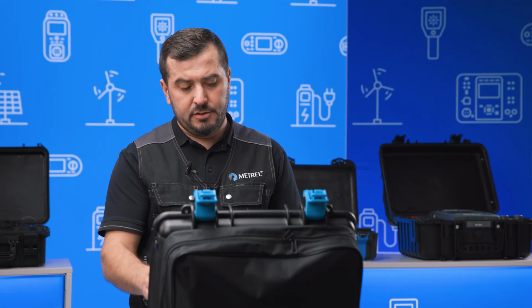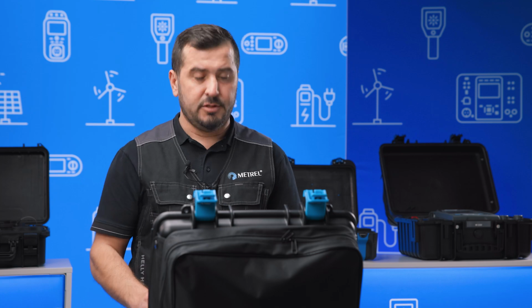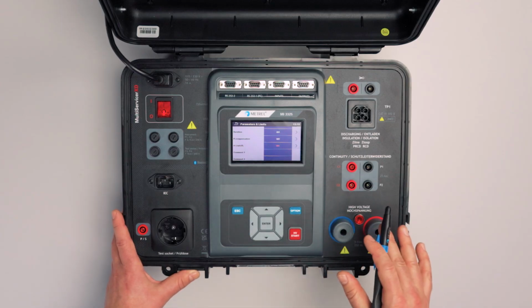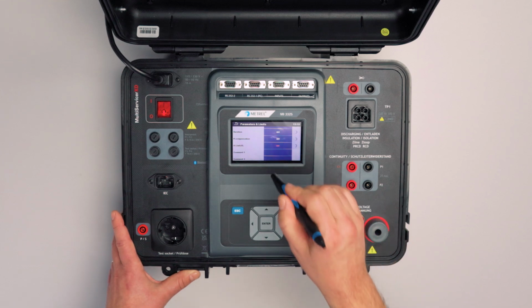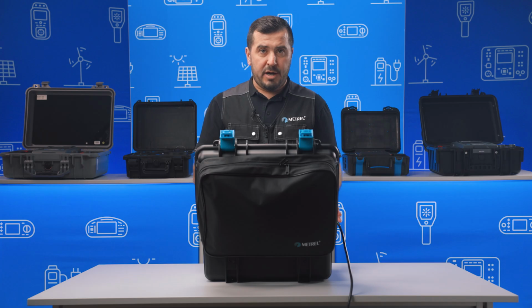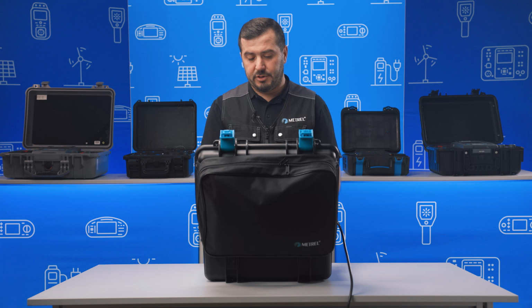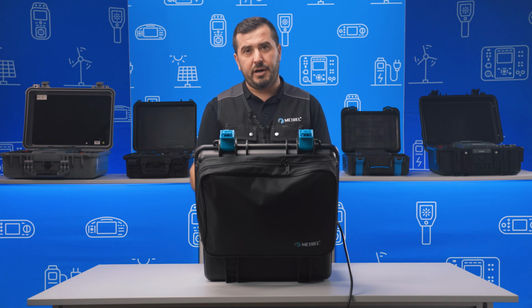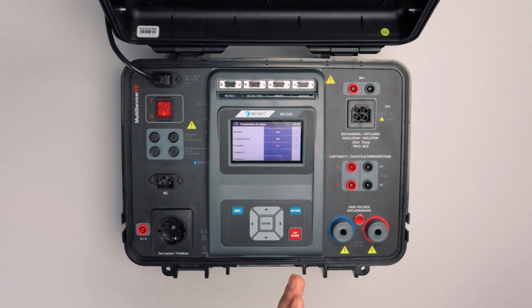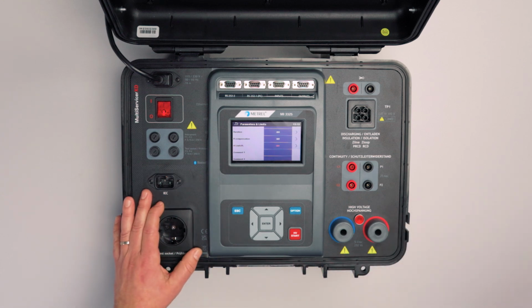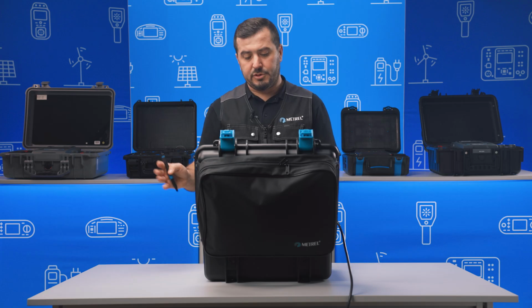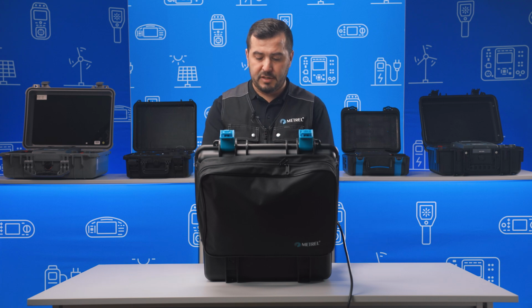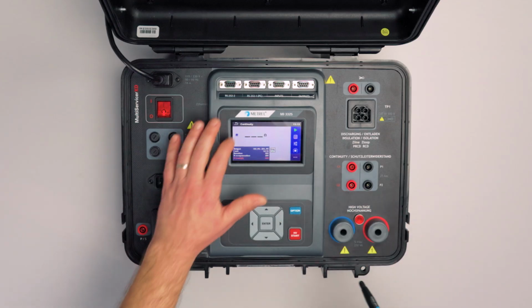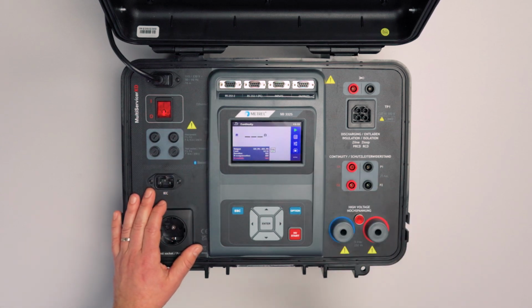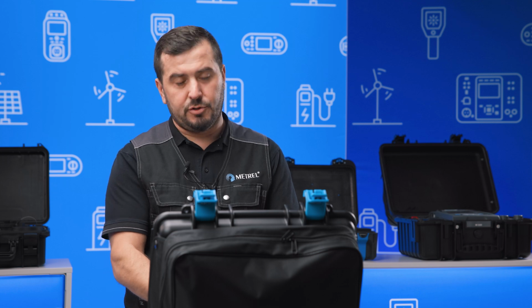We can always set the duration and an additional parameter, the compensation, which enables us to compensate the resistance which is added manually into this field. Why is this feature nice to have or important? It's in case we are, let's say, testing four-wire earth continuity on multiple socket outlets, and we would like to deduct the resistance of these sockets. We can enter it here manually, and of course we do not have to reconnect the test leads every single time. For the two-wire test method, there is also the option of compensating the test leads.